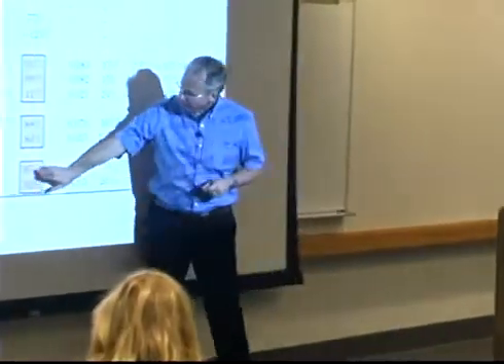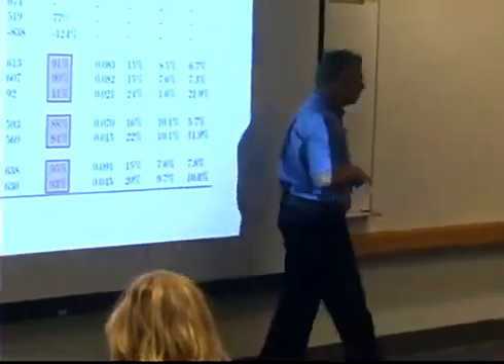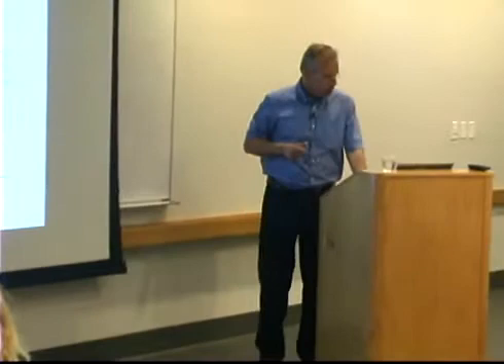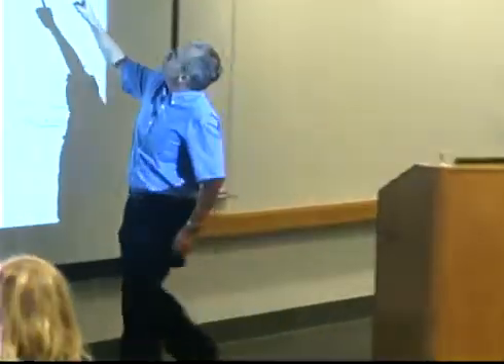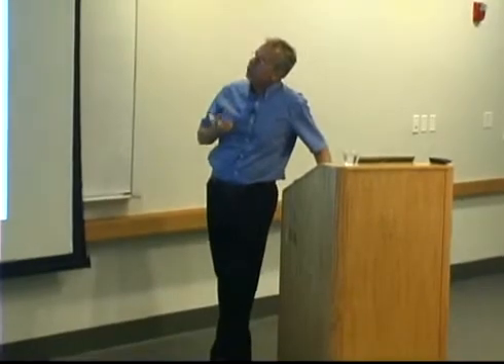And the adaptive boosting techniques outperformed this, but there is a reason we preferred the CARTs, and I'll try to explain why. The CART structure that we got is shown here. It's again one of those dendrograms, and this node up there asks: is the temperature in the second zone in the middle layer greater than 19.7 degrees?